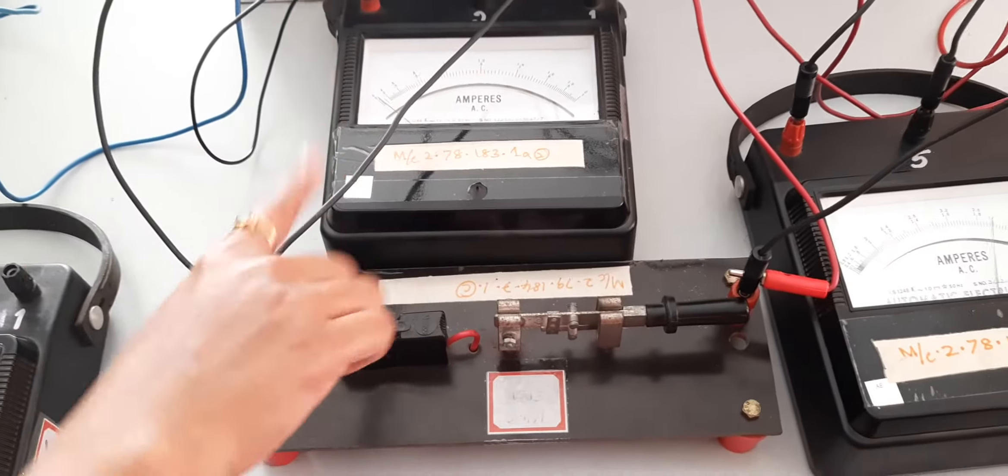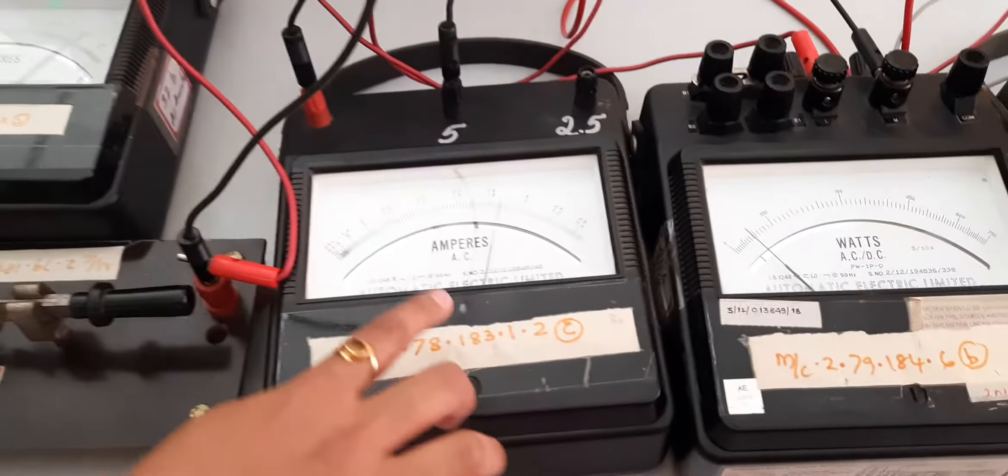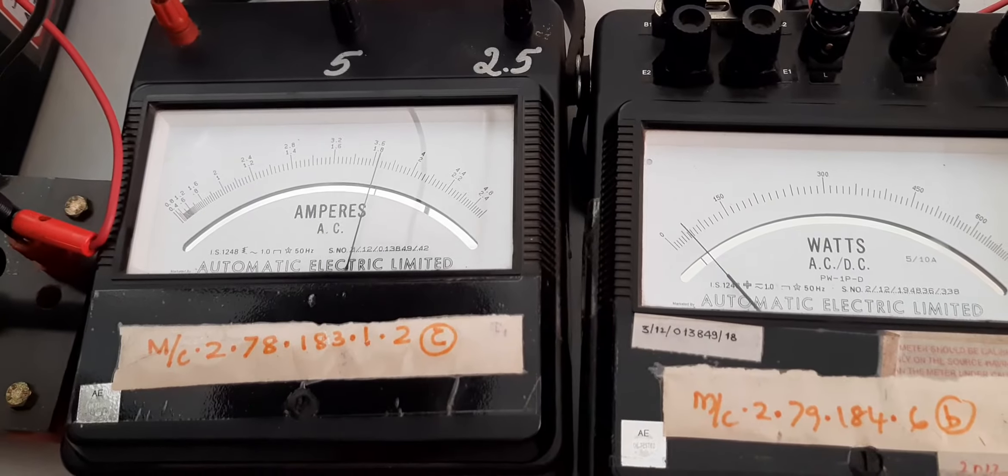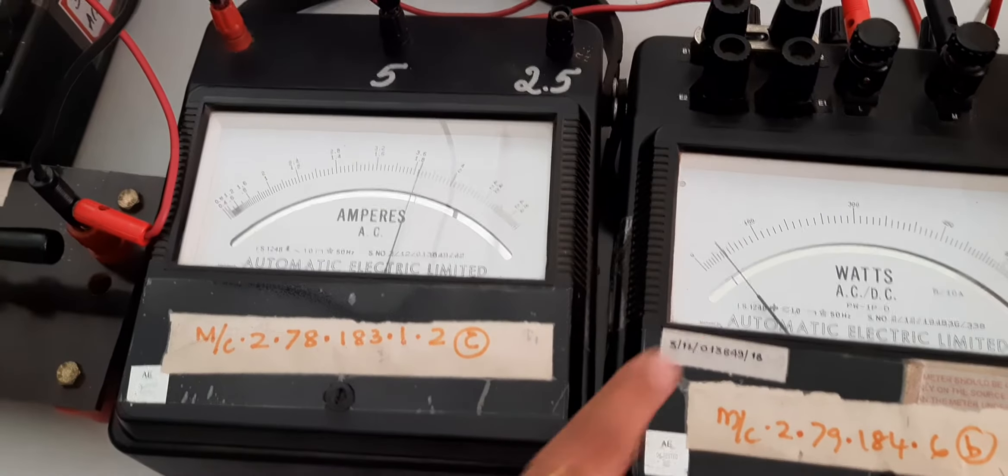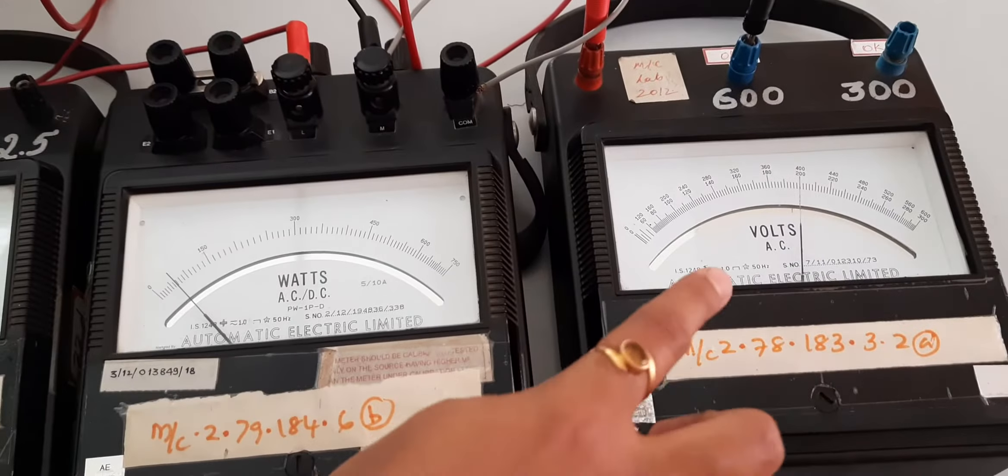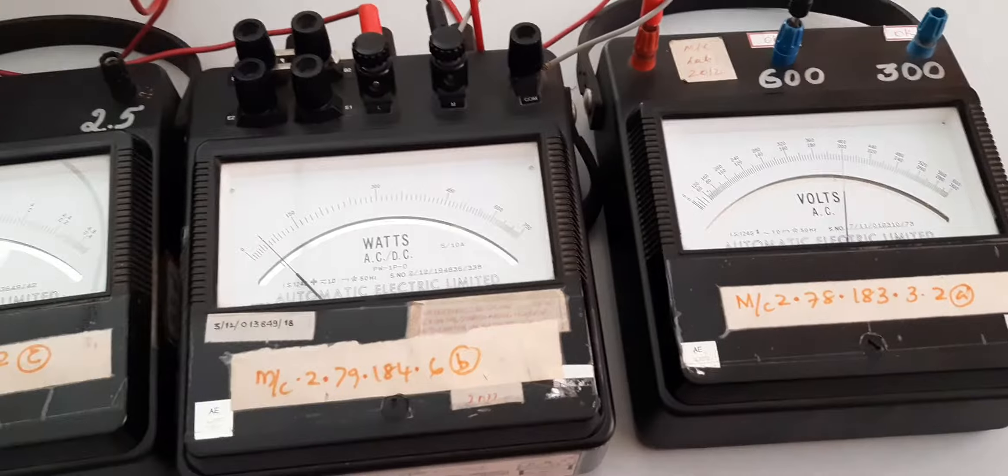This will be taken later. The initial armature current is around 3.7 amps. This is the watt meter reading which reads around 40 and this is the volt meter which will give you 400. This will remain constant.